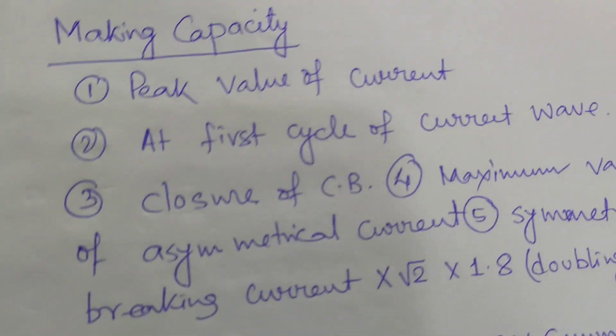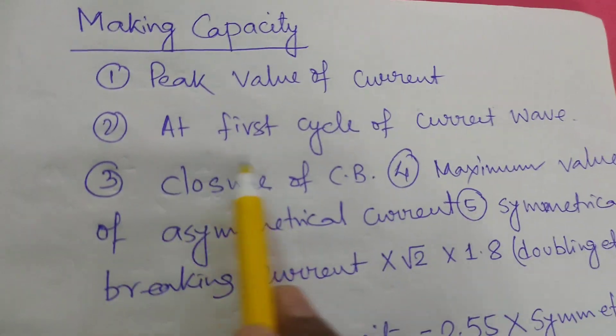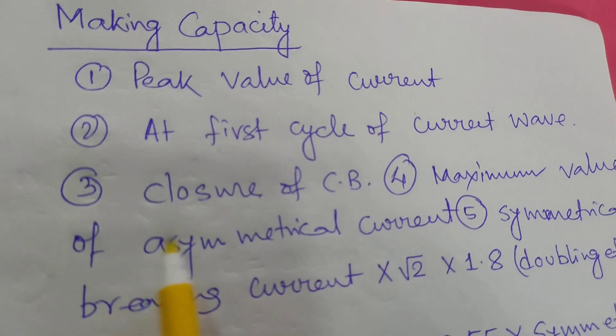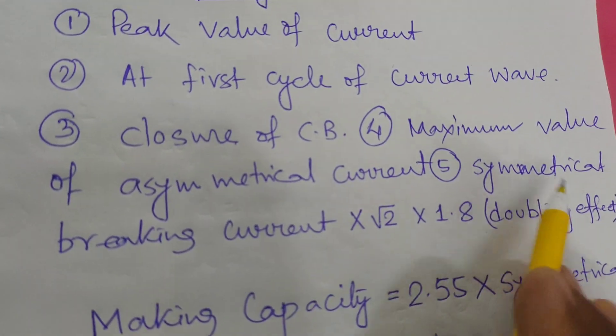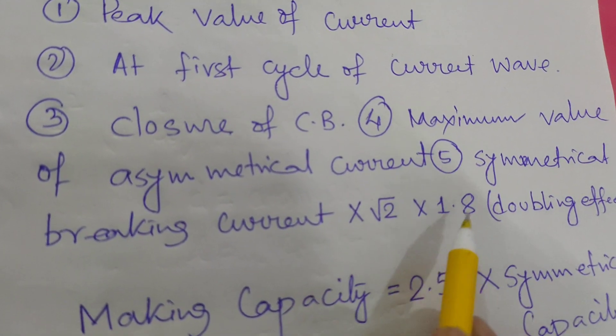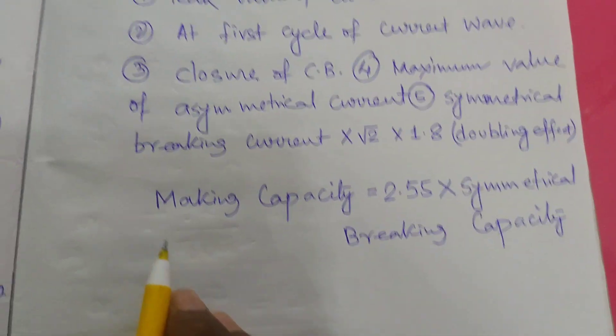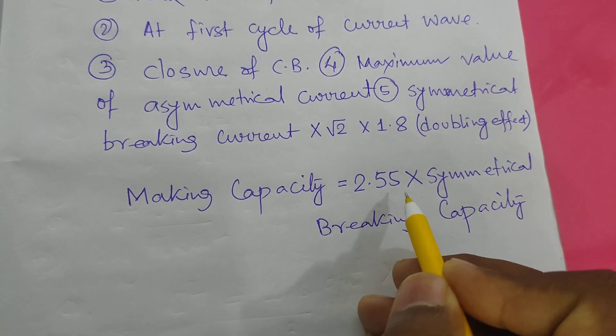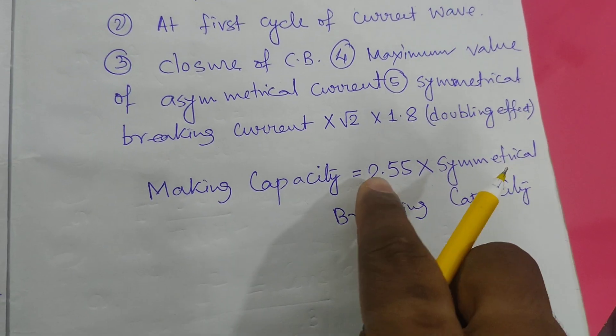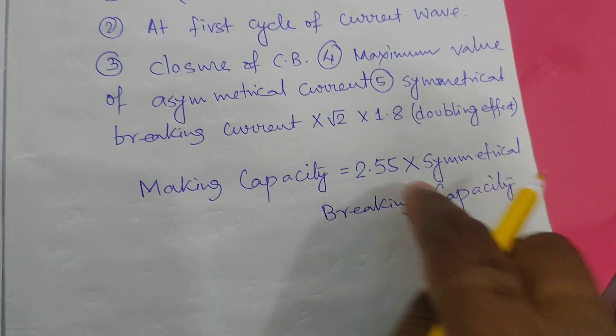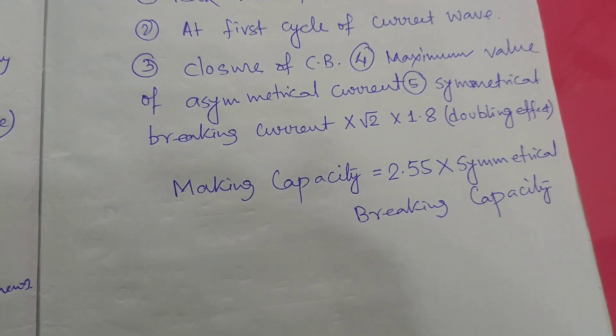Now let's discuss the Making Capacity of the breaker. It is the peak value of the current at the first cycle of the current wave upon closure of the Circuit Breaker — the maximum value of the asymmetrical current. Making Capacity equals symmetrical breaking current × √2 × 1.8 (doubling effect), which gives Making Capacity = 2.55 × symmetrical breaking capacity.